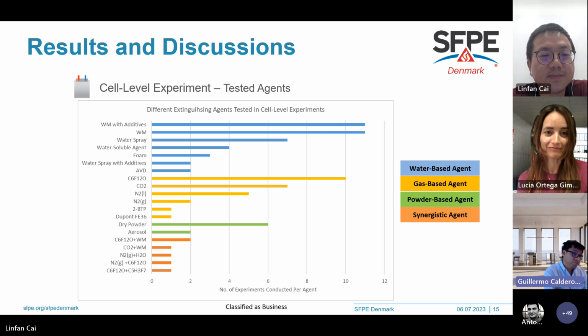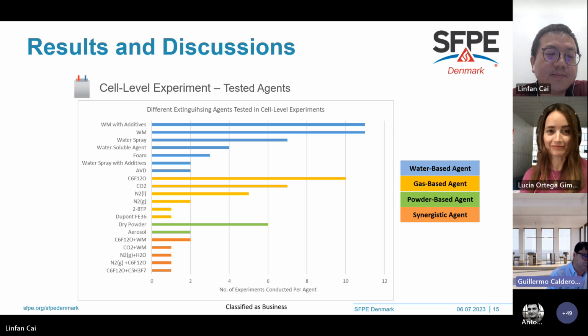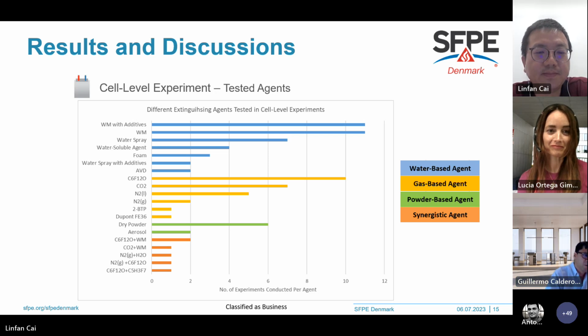We're taking advantage of the cooling effect by combining those two systems in an enclosed containerized energy storage system. The enclosure helps somehow contain the thermal runaway. The requirements are a bit gray in that area for containerized systems, because it says the manufacturer is the one that recommends the type of system, but during several risk assessments we found that you need a water-based system.